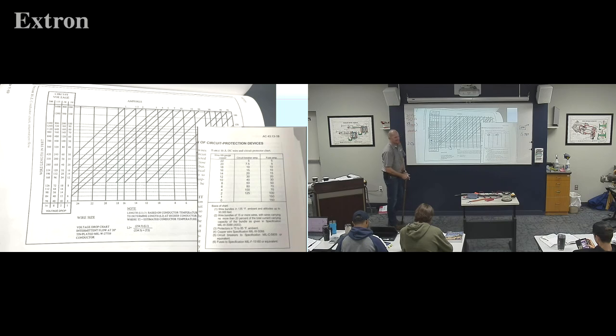So in a sense, the chart doesn't really help you when you're doing the short lengths. It only helps you out once you start doing long lengths and then you get more voltage. Exactly. And that was where we were going: once those lines start disappearing, we're just gonna skip right over to here. So if you get down below where those lines are on your chart, you'll just go straight to what size breaker, because that will end up being the determining factor.